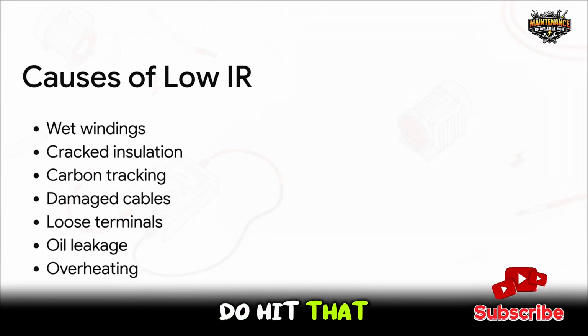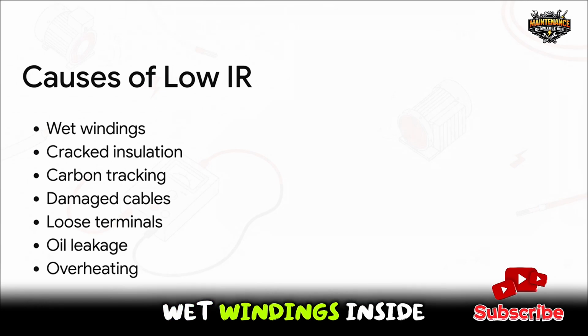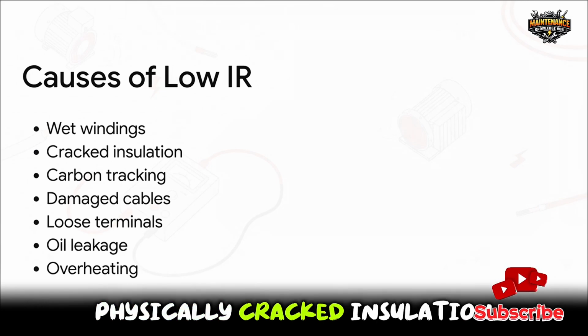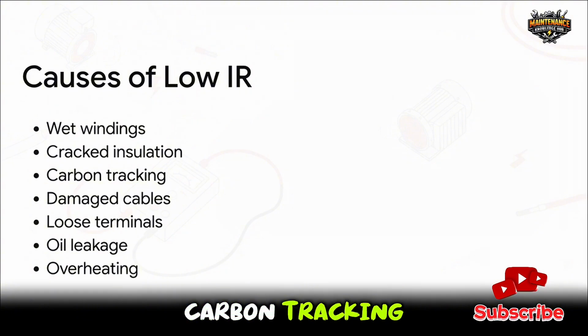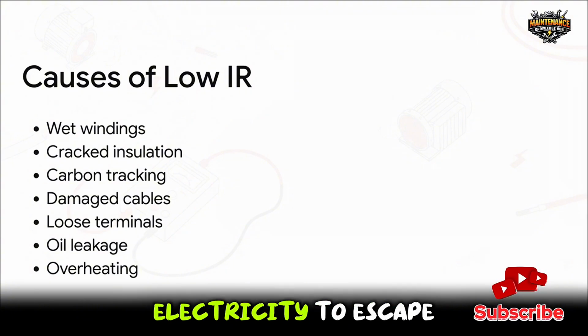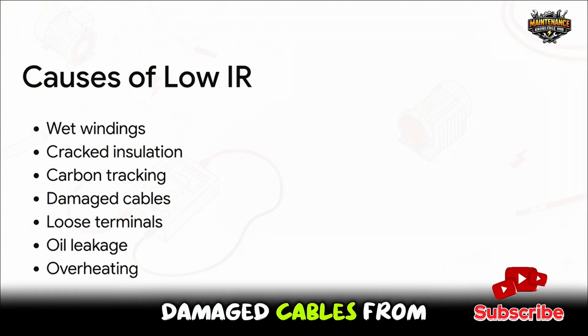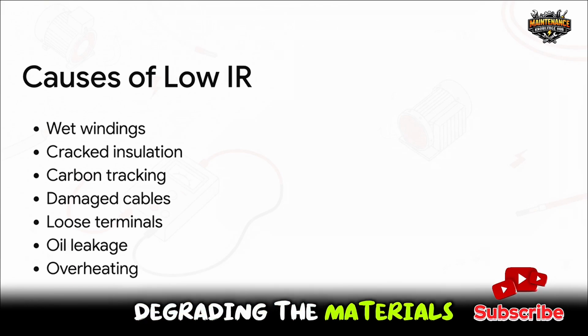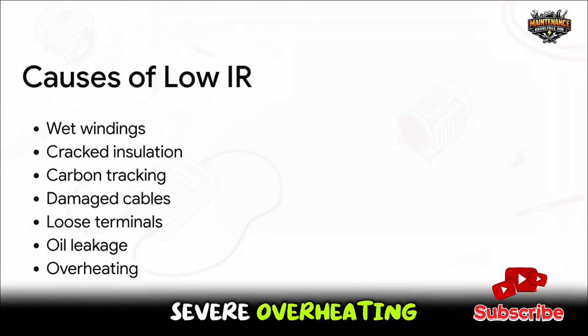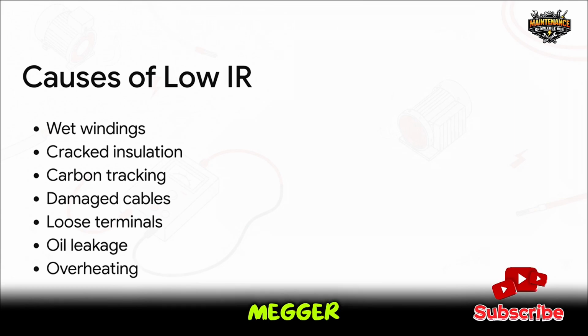Now, if you do hit that scary sub-1 megaohm reading, these are the common physical culprits you'll be urgently looking for. Wet windings inside your motors, physically cracked insulation, carbon tracking which creates a sneaky path for electricity to escape, damaged cables from mechanical stress, loose terminals, oil leakage degrading the materials, or evidence of severe overheating. One of the limitations of the Megger is that it won't draw you a map to the exact fault location, but it definitively tells you that one of these physical problems is present.